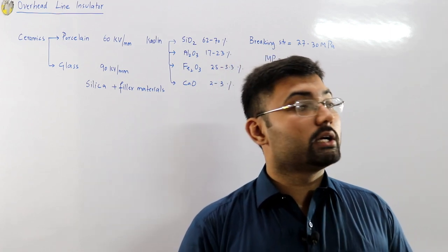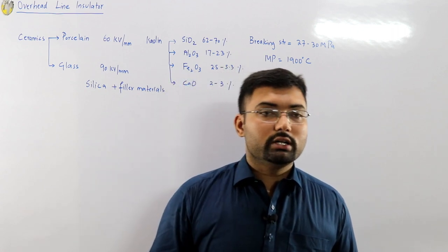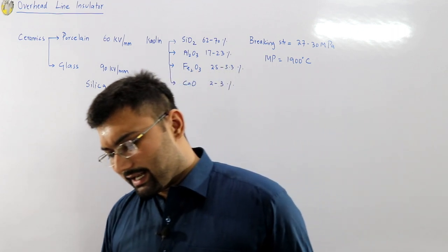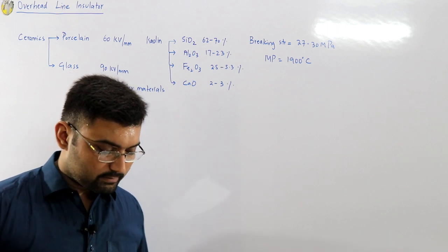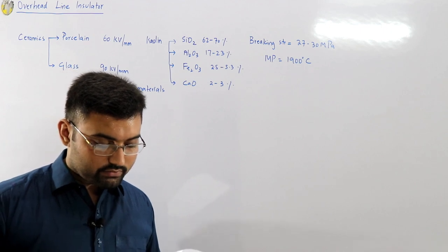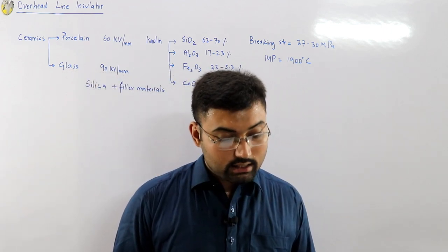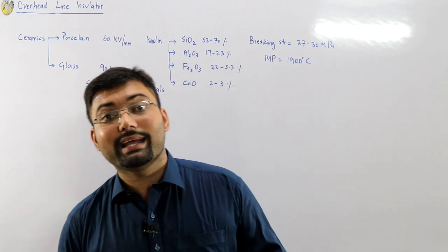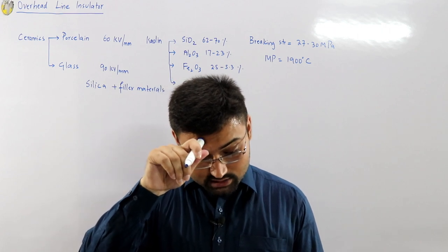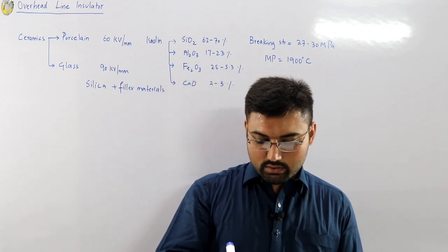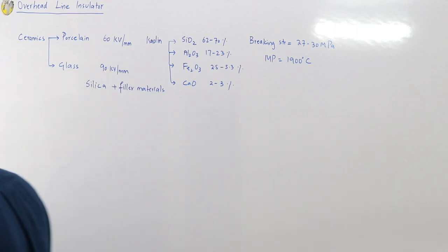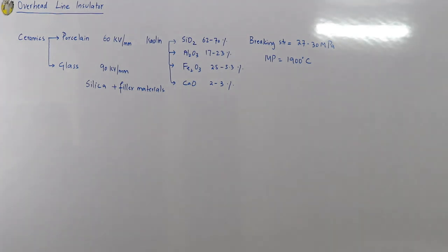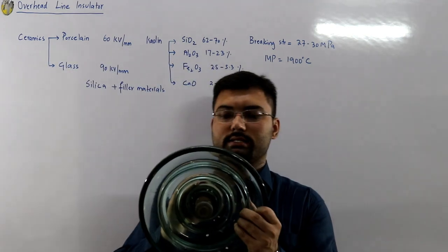In the coming 10–15 years you will stop seeing porcelain insulators and will see glass insulators instead. In 1980 IEC introduced the electrical-grade glass for the first time. One other advantage of glass is that it is transparent, so you can see voids or micro-cracks present inside it.